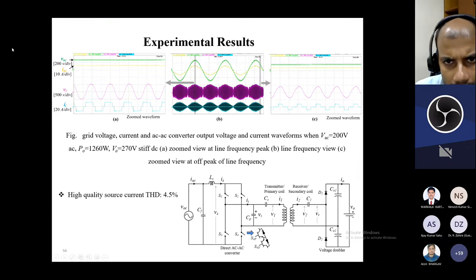The middle diagram shows the inverter input voltage, grid voltage, then yellow grid current, then the matrix converter—or in other words inverter—output voltage and current waveforms, similar to earlier. Here the THD is slightly higher, at 4.5%, but it is still acceptable, below the 5% limit.